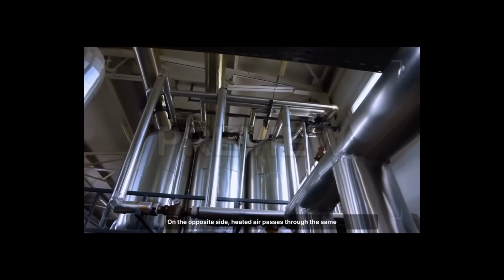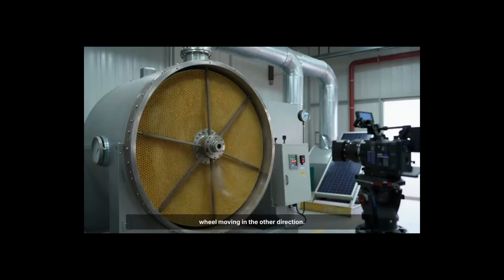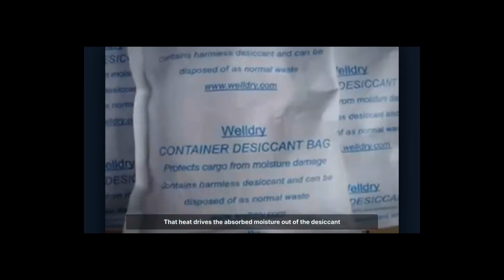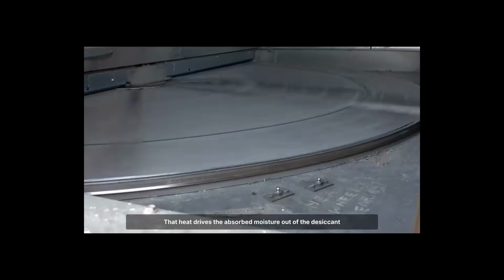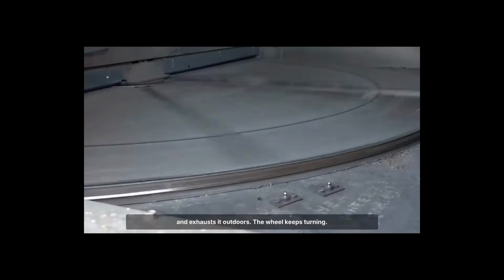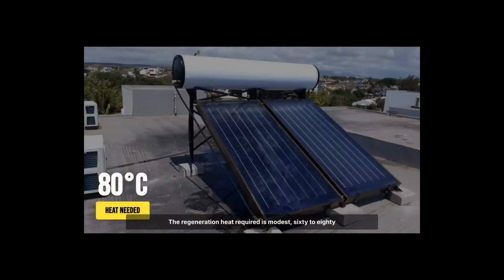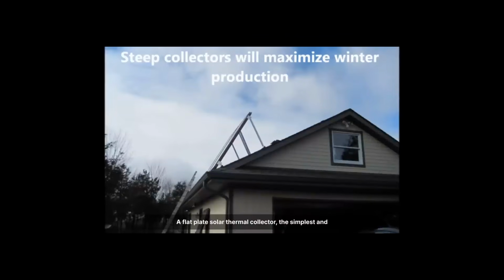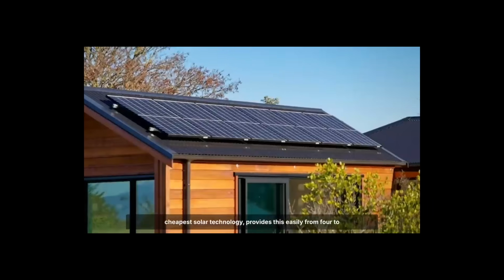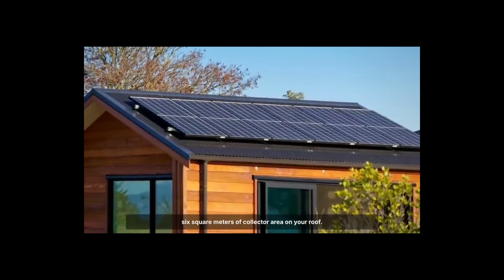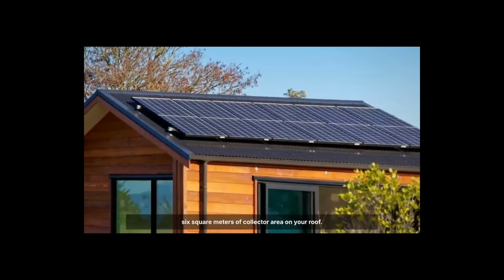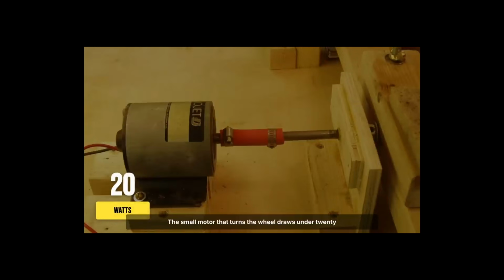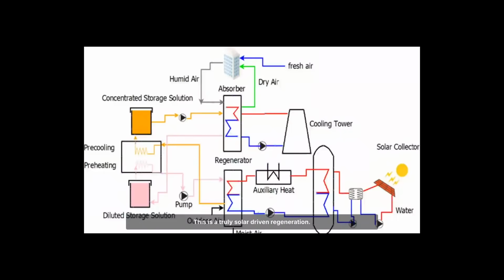On the opposite side, heated air passes through the same wheel moving in the other direction. That heat drives the absorbed moisture out of the desiccant and exhausts it outdoors. The wheel keeps turning. The drying never stops. The regeneration heat required is modest, 60 to 80 degrees Celsius. A flat plate solar thermal collector, the simplest and cheapest solar technology, provides this easily from 4 to 6 square meters of collector area on your roof. The small motor that turns the wheel draws under 20 watts. This is a truly solar-driven regeneration.